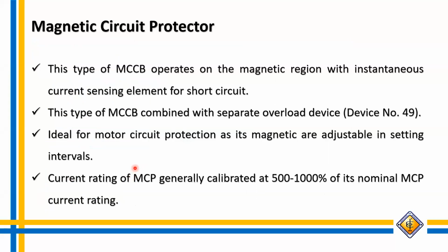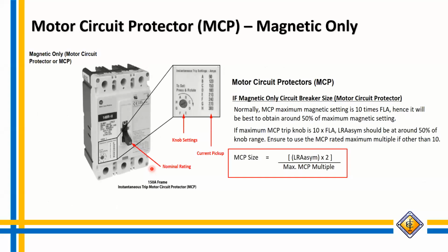So another protection is the magnetic circuit protector. This type of MCCB operates on the magnetic region only, okay, with an instantaneous current sensing element for short circuit. Then we have this magnetic circuit protector combined with a separate overload device, or device number 49. Ideal for motor circuit protection as its magnetic trip is adjustable in setting intervals, and the current rating of the MCP is generally calibrated at 500 to 1000% of its nominal MCP current rating.